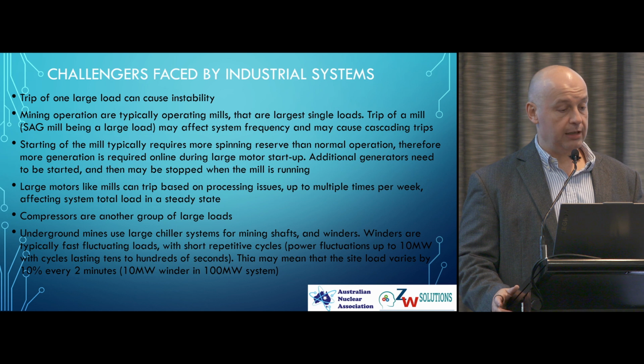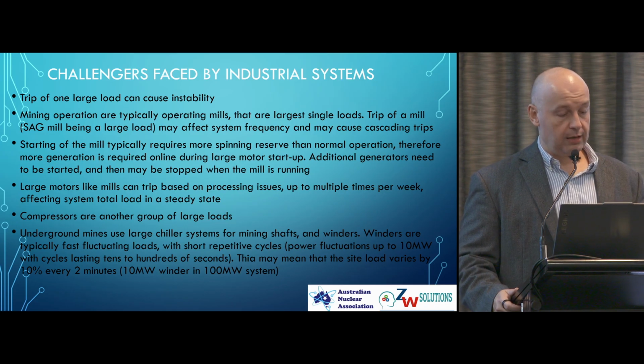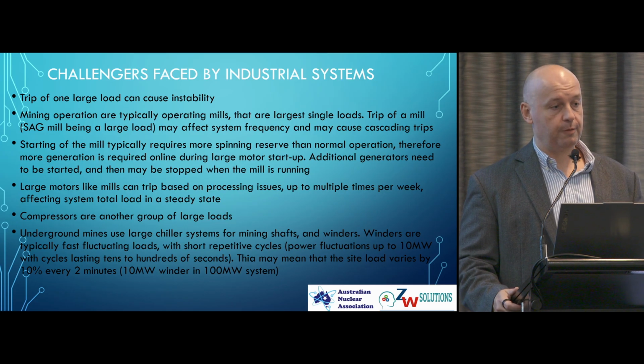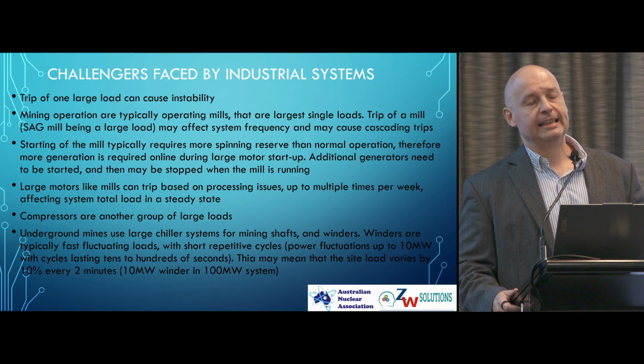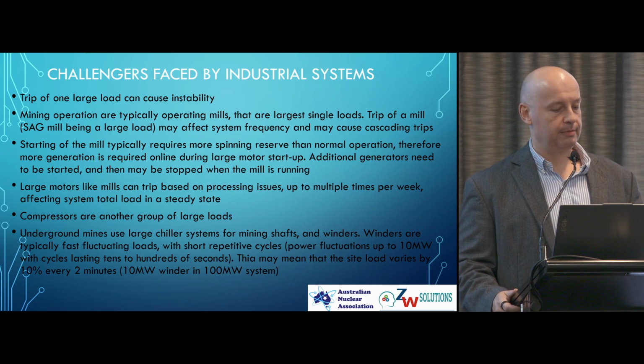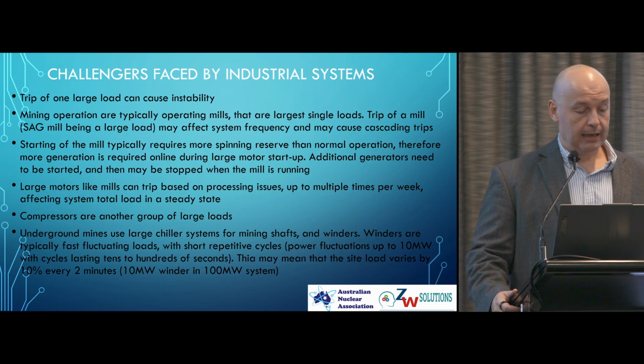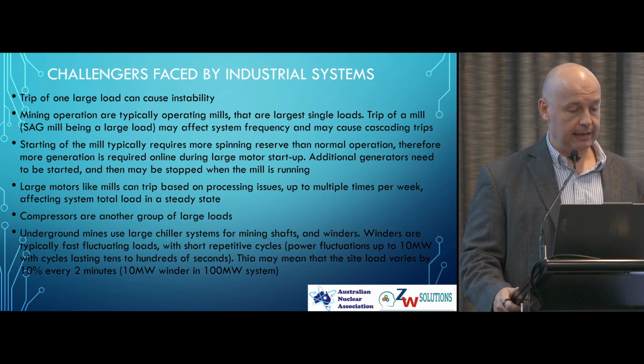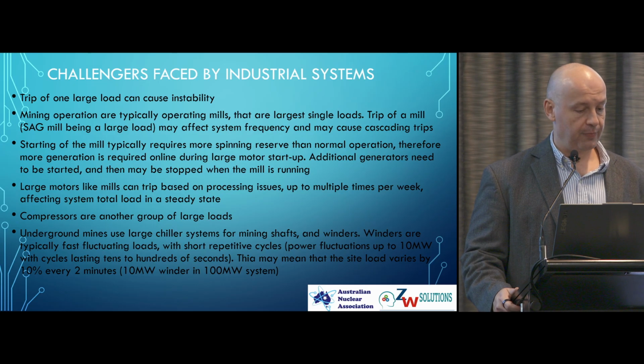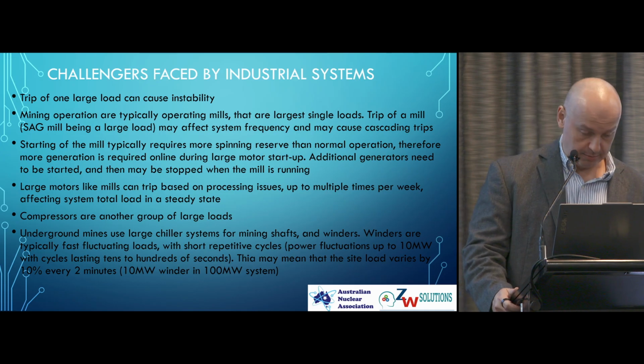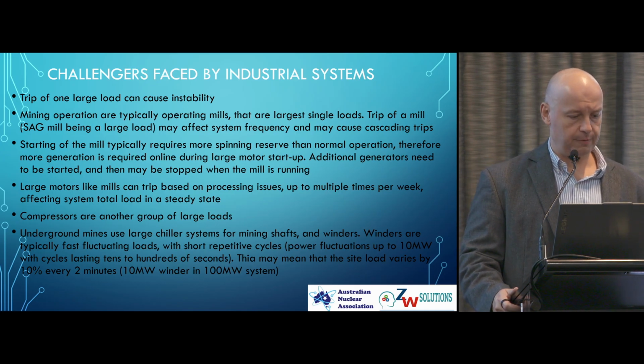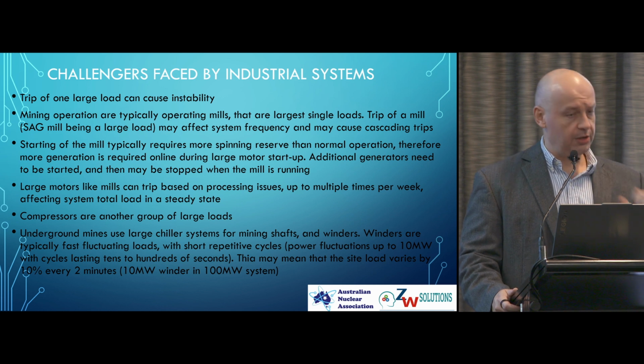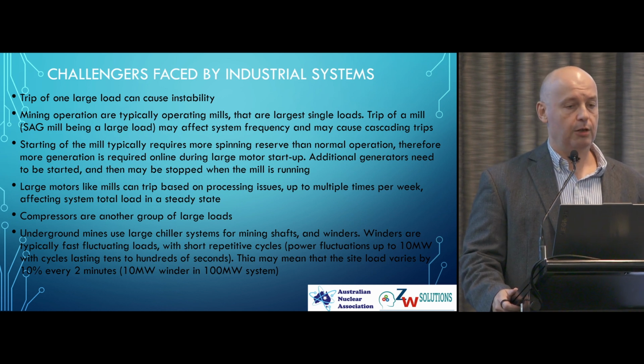So again, in a mining operation, typically the biggest loads are mills, and they are affected by system frequency. So if the system is unstable, which renewables are well known for, they will trip. That's the thing. The other types of loads are the compressors. If the mines are using underground operations, they have large chilling systems and the winders.